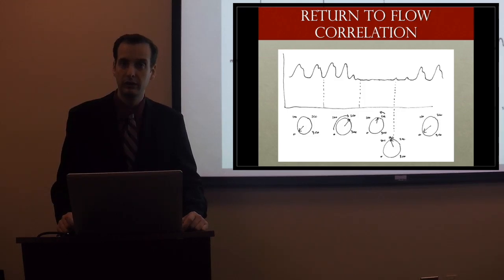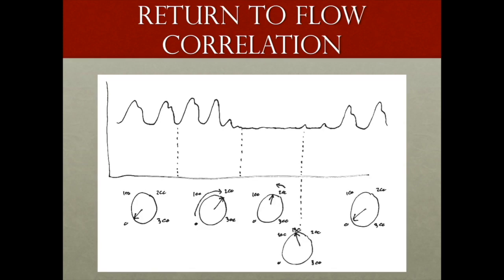You then slowly release the pressure within the blood pressure cuff while looking at the monitor. When you see the first blip of the arterial tracing returning, you reclamp your blood pressure cuff and look at the needle position on the sphygmomanometer. The pressure on the cuff that correlates with the return to flow will tell you what your true arterial pressure is.